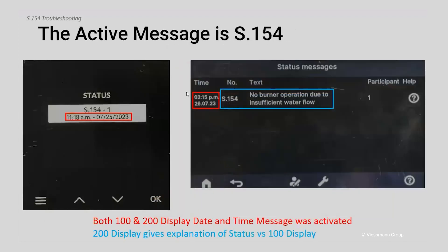Here I am in active messages on the 100 on the left-hand side, and you've got the 200 control interface on the right. With every message you get, all messages are going to be date and time-stamped. We always put a date and time in the boilers — not just for timers but so that when you have active messages, you get an idea of when those issues are occurring, what dates and times. You might find some commonality there as long as the time and dates are accurate when you do your programming.